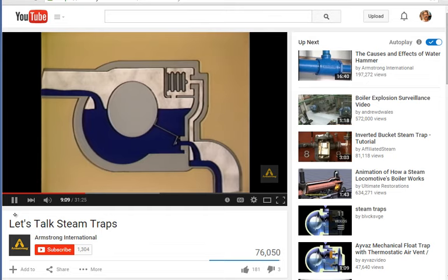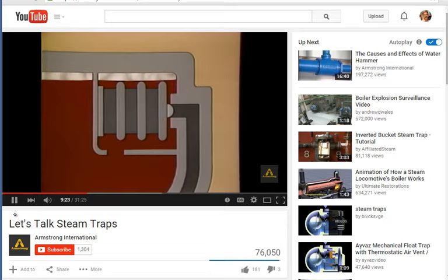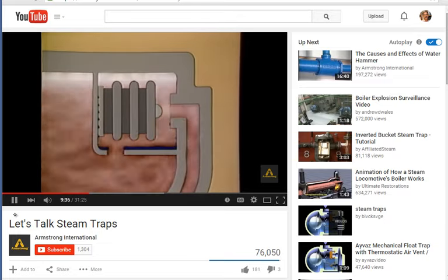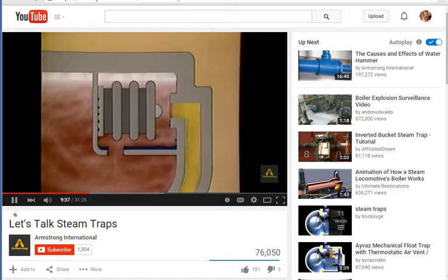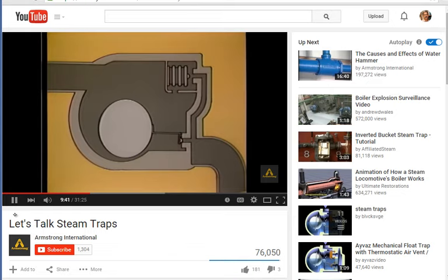the valve. Above this seal, near the top of the trap, is a thermostatic bellows. The bellows responds to temperature change. When this space is filled with hot steam, the thermostatic valve is closed. Non-condensables, such as air, mix with the steam and cool the space near the top of the trap. When the bellows element cools sufficiently, the thermostatic valve will open and vent these gases into a passage leading to the trap discharge. At startup, the float is down, the float valve closed.